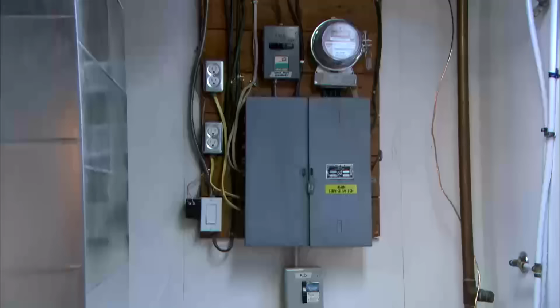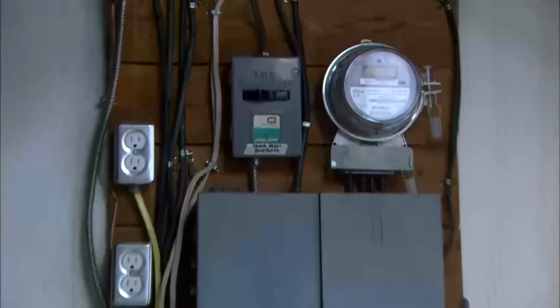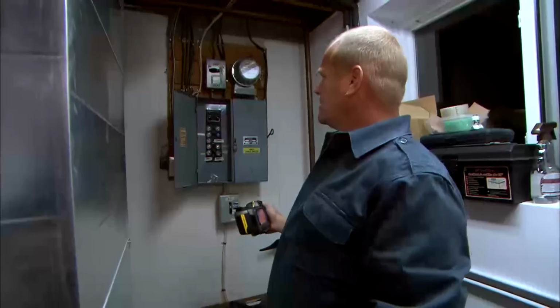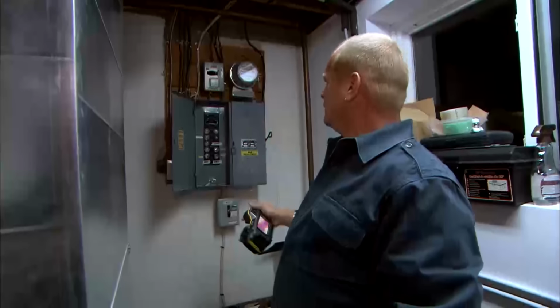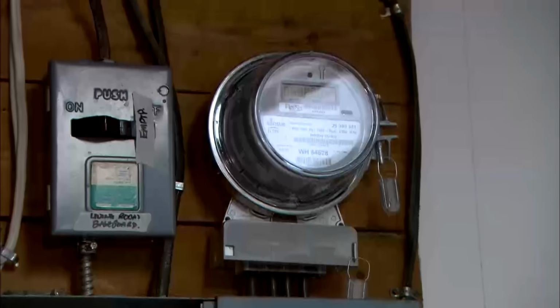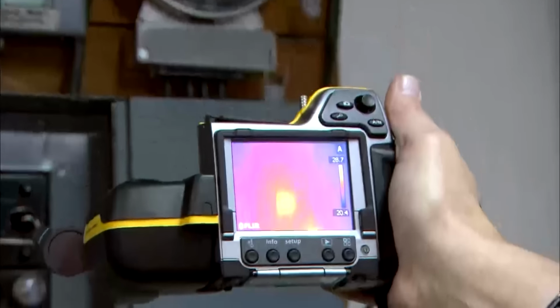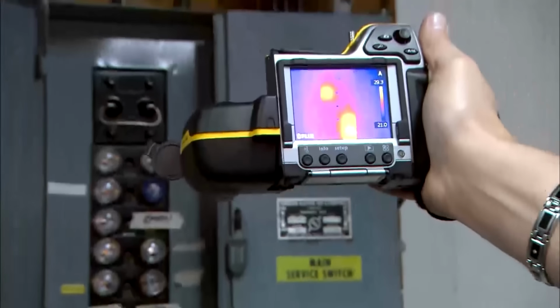We have the meter on the inside of the house, and it's a new meter. Normally, we want those on the outside of the house. In this case, they now got to come inside to read the meter, which I'm sure they're not too happy with. I'm going to use the IR camera. I want to see just how hot the box is. Ooh, not a good sign.